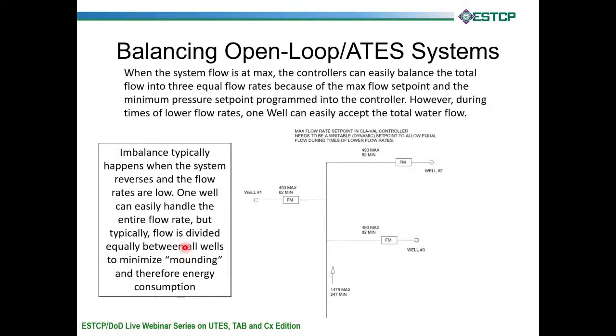So that helps to keep our flow equal for the most part. In this diagram, this shows the project in Pensacola. Our cold wells would have been down here somewhere, and these are our warm wells, and at max flow, we're at 1,479 gallons per minute.